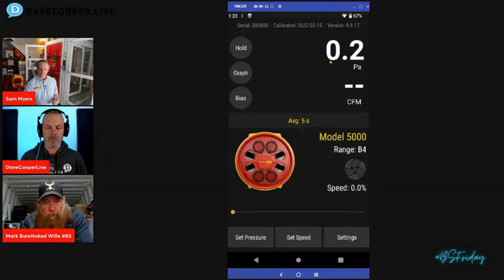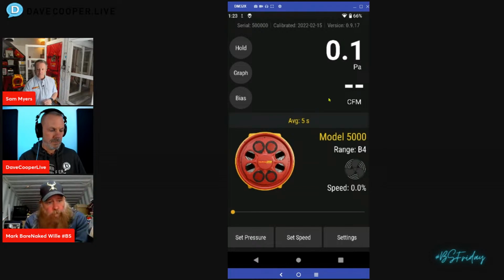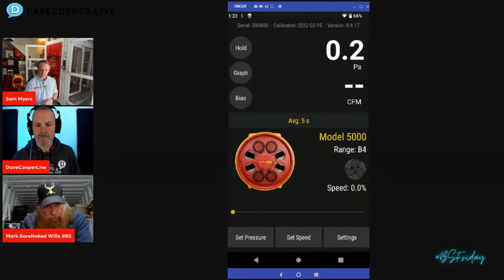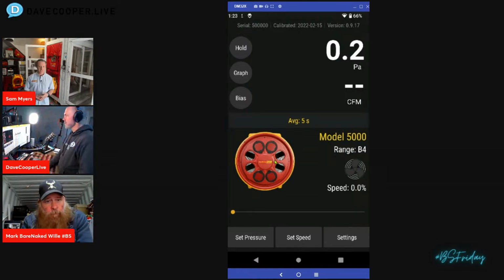This is what we call a 2-channel manometer. One side reads the house pressure with respect to outside, the other side reads the fan pressure. Since we know the fan pressure we're measuring, and we know the surface area of the holes on the inlet side of the fan - like these 4 you see here - we can calculate flow. The gauge just does that for us.